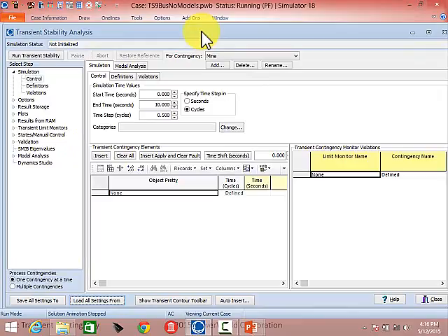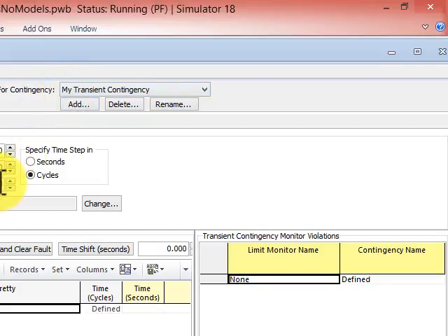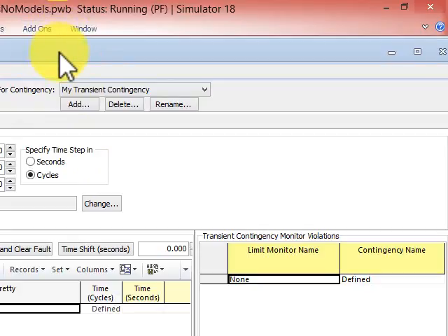There's a question about verifying that no generator is ringing out before running contingencies. If you run a case with no events, it should run flat. However, if there are unstable modes — eigenvalues in the right half plane — they will tend to get excited just by the normal jitter in the solution and you'll see growing oscillations. Running the initial two seconds and checking that it's flat is how we validate. If it's not flat, we're concerned.